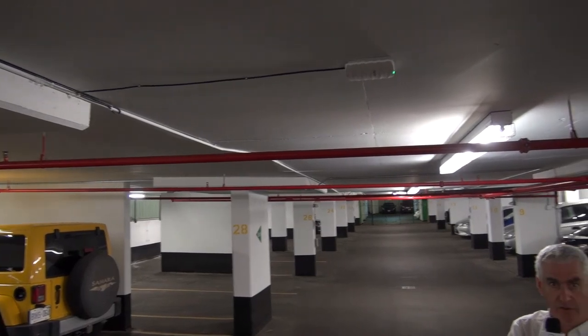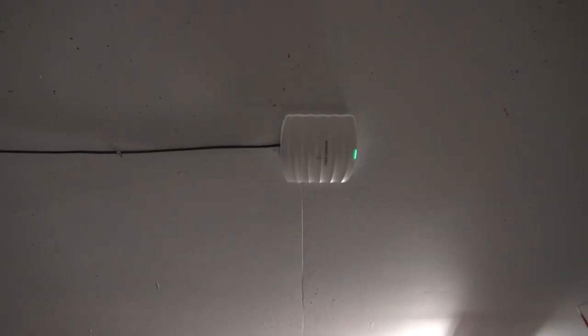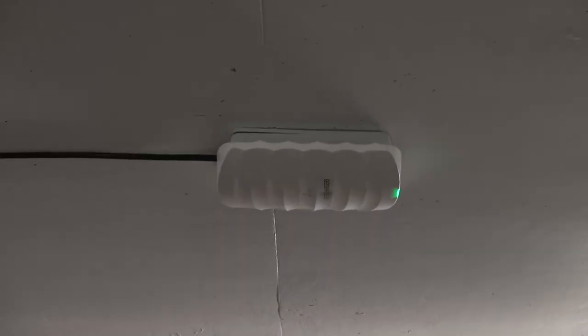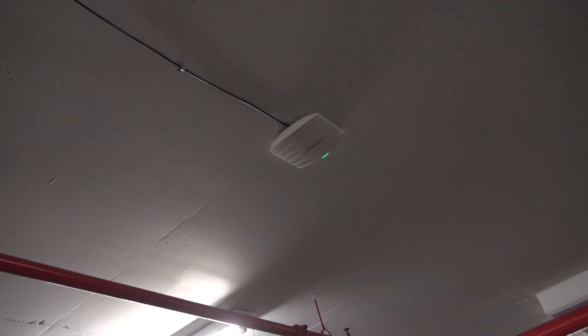Down at the P3 level, we're not getting any outside signal. These antennas are not Wi-Fi for residents' phones — they're machine-to-machine, strictly to pick up the signal from the charger and deliver it to the internet. Installing the panels, transformers, and antennas was part of the infrastructure the corporation would typically pay for. From the panel to the charger, that's what the resident would pay for — they own the charger and cover the piping and wiring. Some runs were a little closer, some a little further, but they fall into a standard range, though everybody gets an individual price.